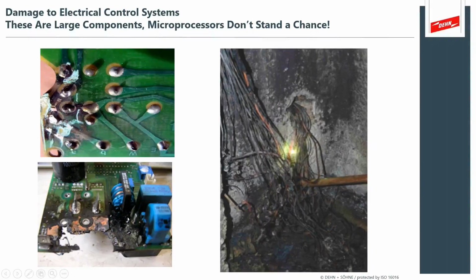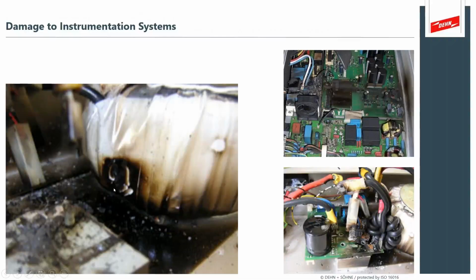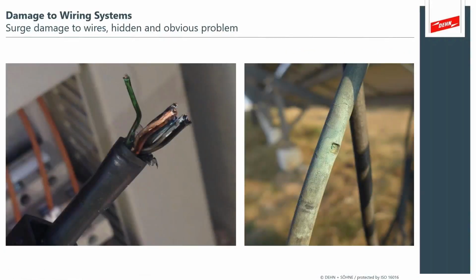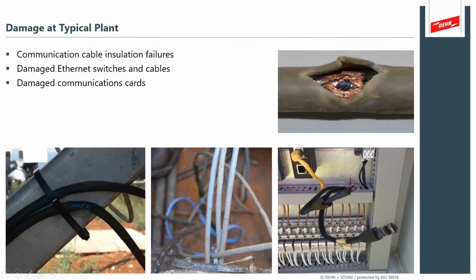It can be very obvious. Here we see transformers on fire, and here you can see vast damage from one of the cables. It might have had a problem, but the result is damage to all that I/O wiring. You see very obvious transformer damage on small power supplies. You can imagine what it's doing to a microprocessor power supply. You can see the damage. It blows the jacks off of these RJ45 type power over Ethernet circuits. You can see it actually cause a small burst in the earthing and shielding on a cable. When there's enough surge, it'll blow the jack off. When there isn't enough surge, it will essentially be absorbed into the rest of the equipment, and so those stresses are happening to your cabling, and over time or through one event, you can see that you can actually have the jacket burst and arc into the shielding, arc into the actual data cables.